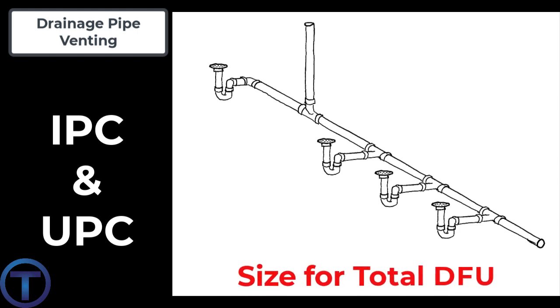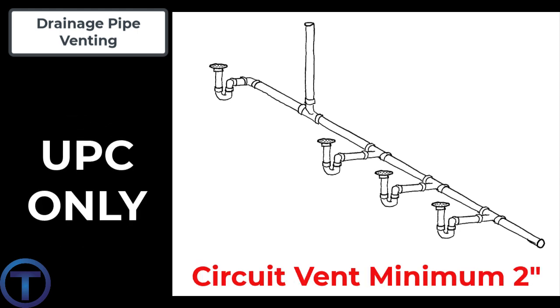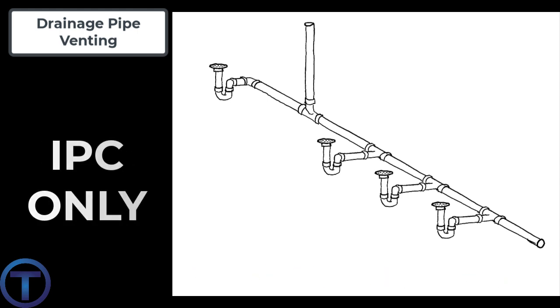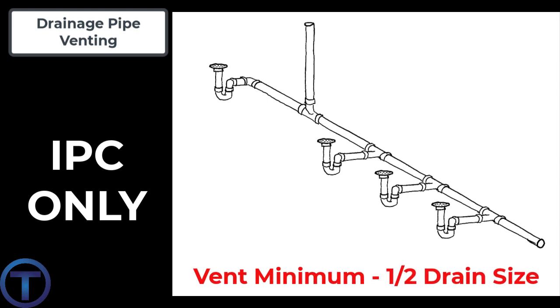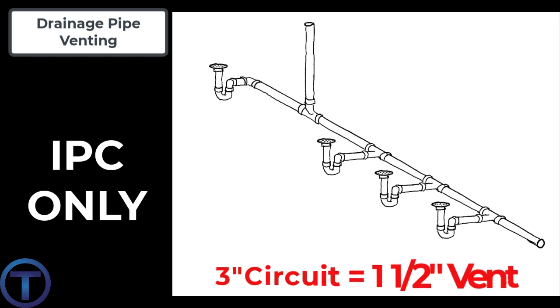When it comes to sizing a circuit vent, both the International and Uniform Plumbing Codes state that the size must account for the total drainage fixture units connected to the circuit. This is basic drainage sizing from chapter 7 in either codebook. There is one additional note from the Uniform Plumbing Code: the circuit vent must be a minimum of 2-inch pipe. The International Plumbing Code states that a vent must be at least half the diameter of the drain it is serving — so a 3-inch circuit could have a 1.5-inch circuit vent.